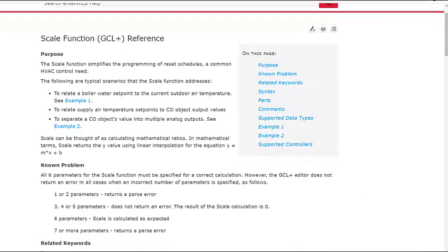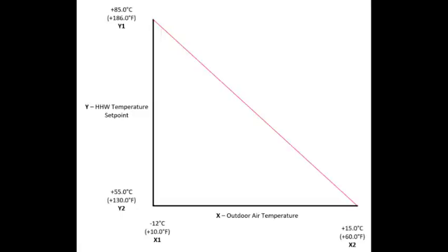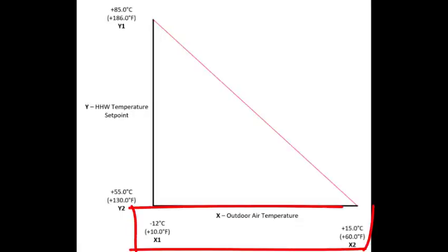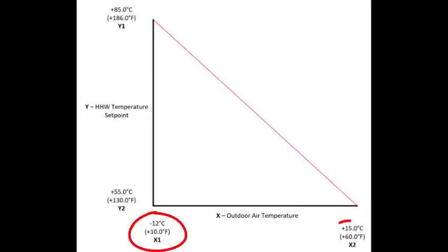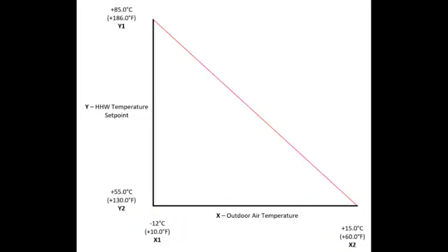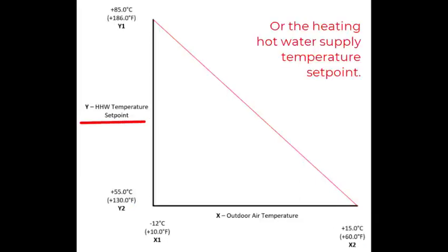Graphically, it looks like this. The values on the lower axis of our graph are the outdoor air temperature sensor readings. And the two values are the min and max range we need to react to. On the left hand side is the calculated heating hot water supply temperature set point.